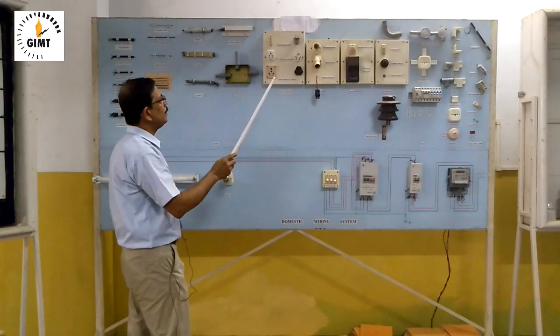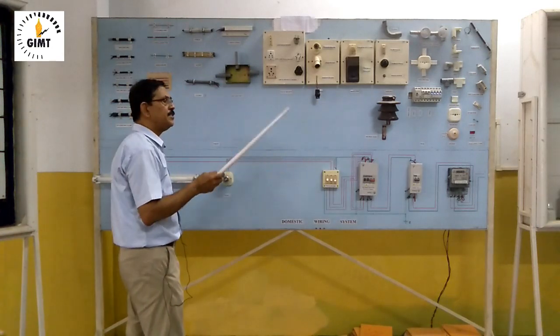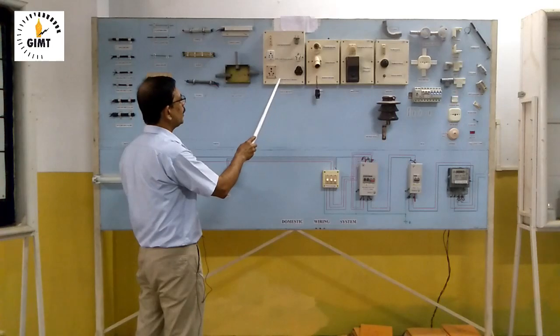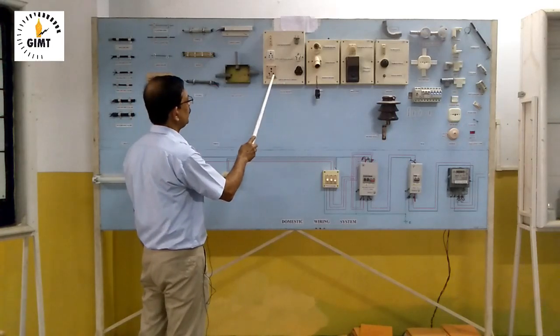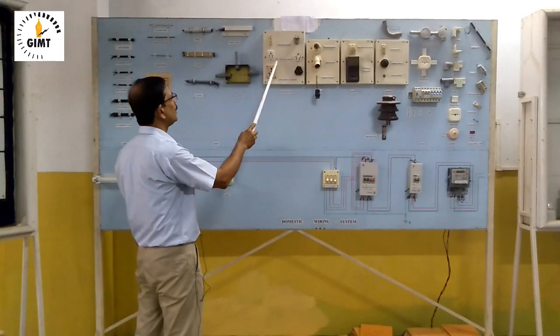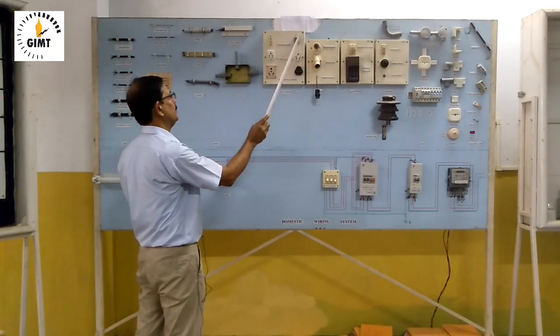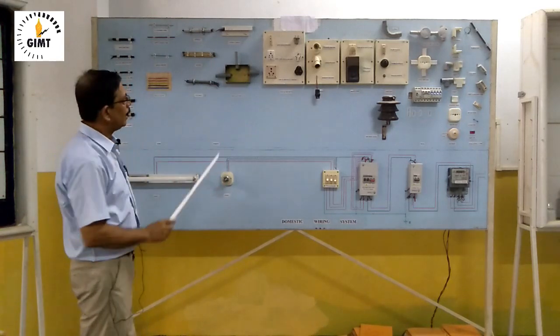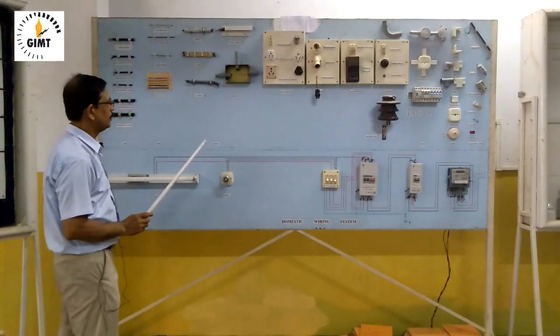So when you are using like heater, geyser, you cannot use this. You have to use more current rating plug and socket. So in that case you have to use three-pin 15A. And in general we are using three-pin 5A. So as per your requirement you have to select the ampere range of the socket, plug and socket.